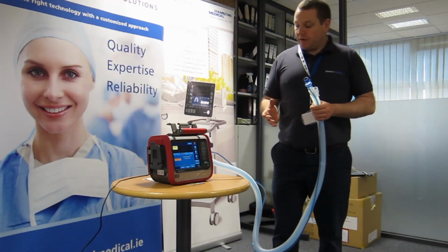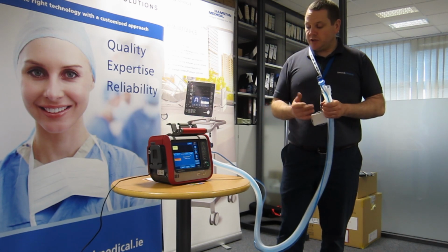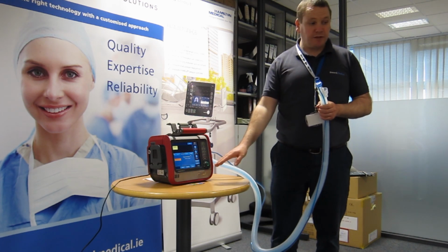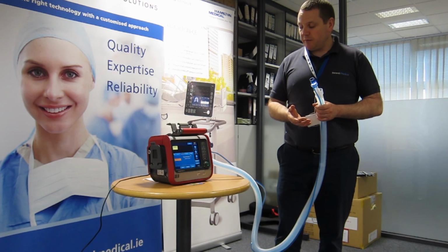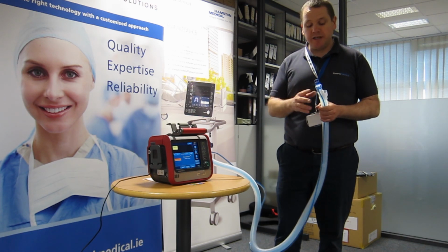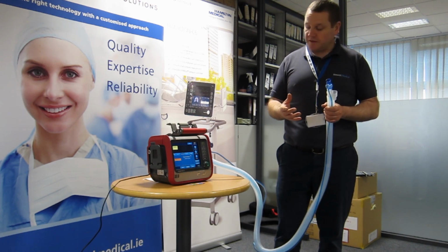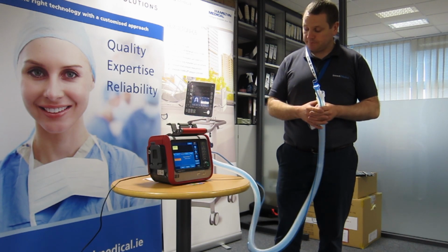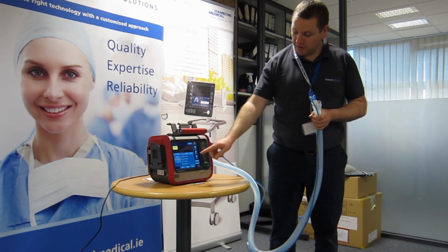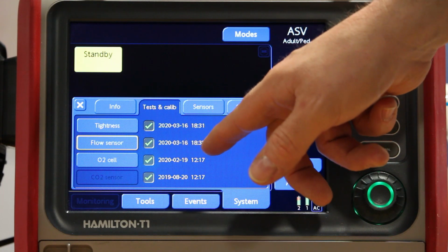So if it does fail the flow sensor calibration, we'd say to do it again, paying attention to the prompts on the screen. If the flow sensor calibration fails a second time or a third time, you may need a new flow sensor, but we've never come across them failing out of the packet, ever. And then we have our green tick and the date and the time.